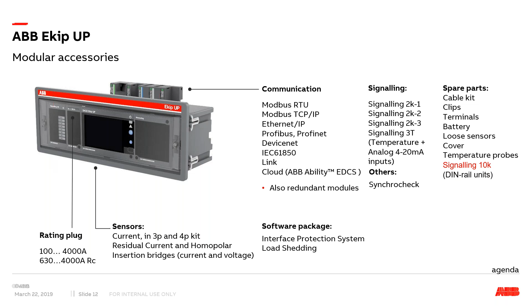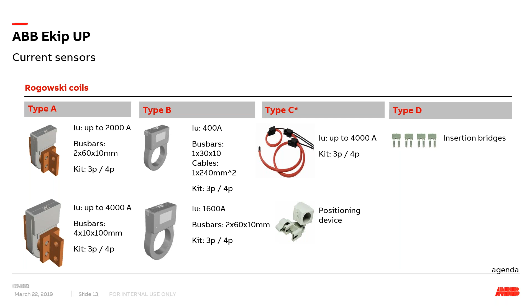Essentially, type A is your typical old school bus bar sensors. Type B is the closed loop sensors that you can run cable, or you can even have bus bar across. My most favorite one is type C, and this is what we designed the most across in Australia. It's an open Rogowski coil, and it's quite easy to install, and you can wrap that around the cables or bus bar wherever it is.